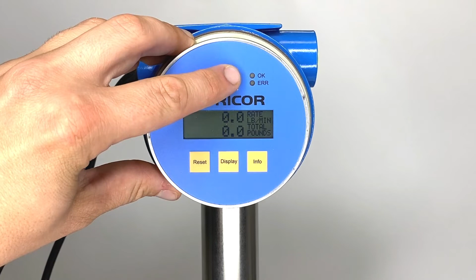At this point, you will choose your type of averaging. To initiate the 0-point calibration, press the slow key for long averaging or the fast key for short averaging. We recommend slow averaging when setting up the 0-point calibration for the first time, and fast if you simply want to verify your calibration.